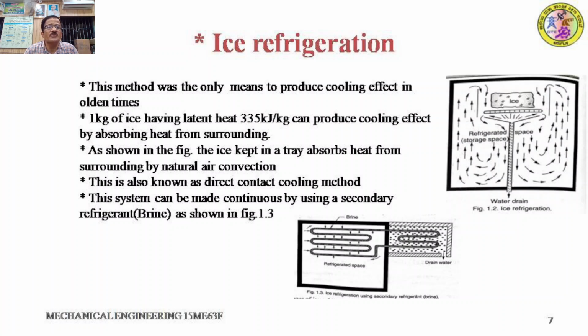I would like to point out that 1 kg of ice, having latent heat of 335 kilojoule per kg, can produce cooling effect by absorbing heat from the surroundings. Usually, in order to produce 1 kilogram of ice, you have to remove 335 kilojoule of heat from it, and for cooling by ice, that much quantity of heat can be absorbed by the ice theoretically, but practically it may be a little lesser than that.